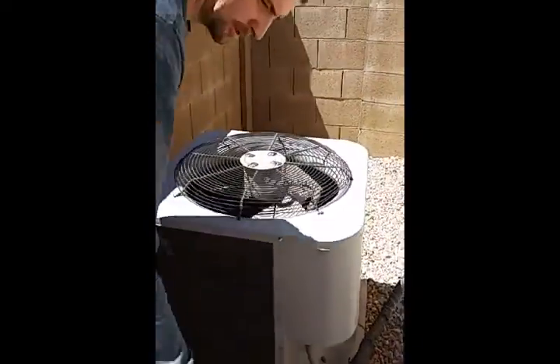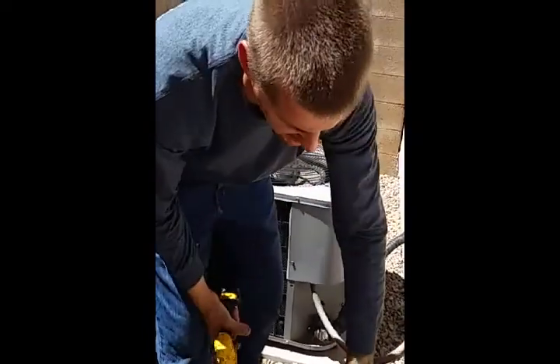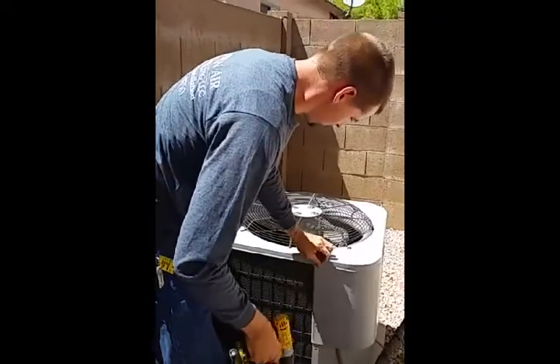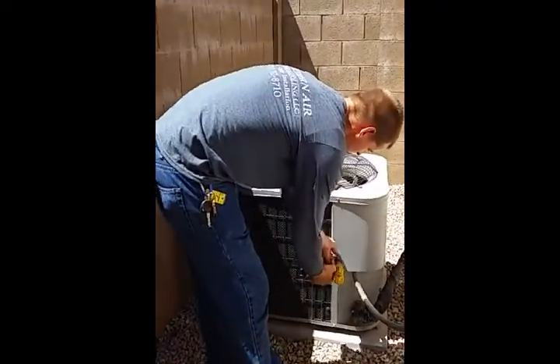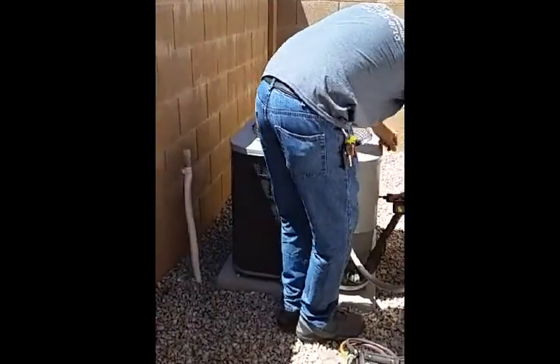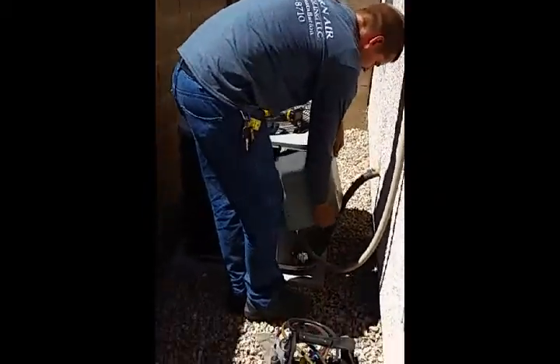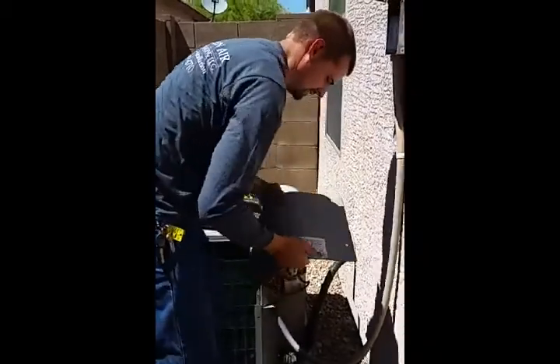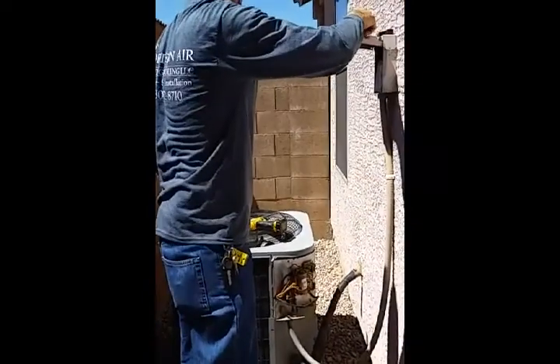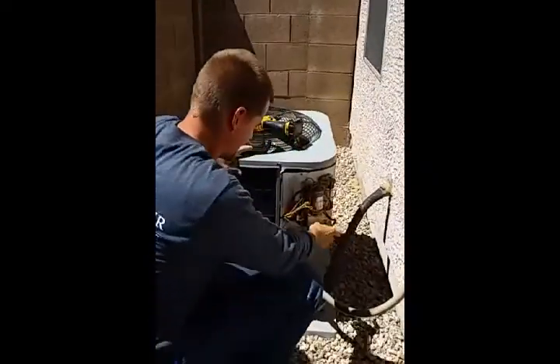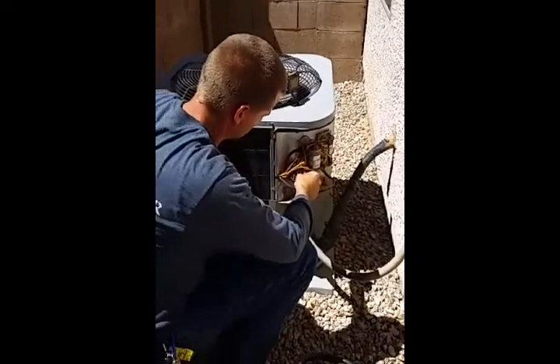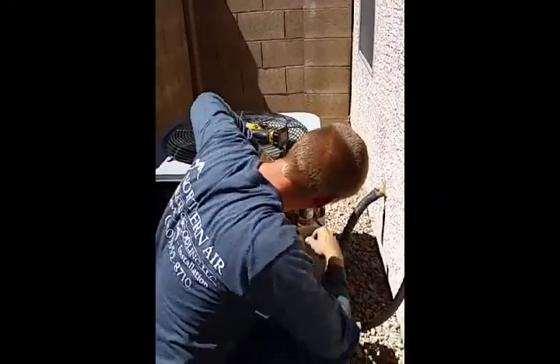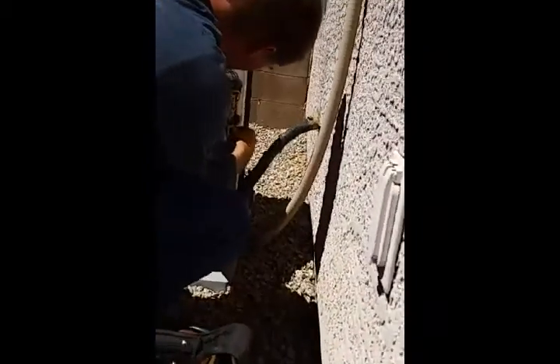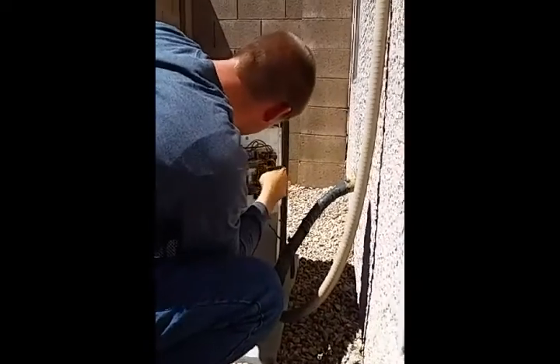And then what you want to do is make sure that nothing is in the way of your fan blade. The last thing you want is to start up the system and blow the charge through the fan blade hitting your copper lines. Like I said, this is a newer style home. It is a Airflow Lennox 4-ton heat pump. Basically what we want to do here is just go over all the electrical connections, test the capacitor, look at the contactor, make sure there are no signs of pitting. Again, this overall looks to be in okay shape. There are no obvious signs of any wear.